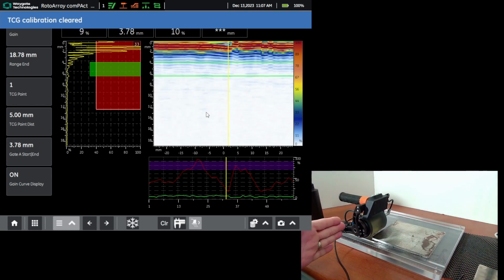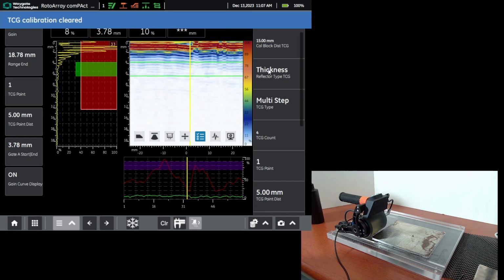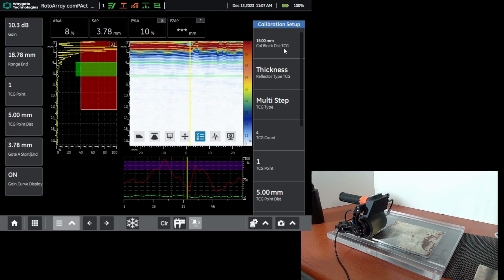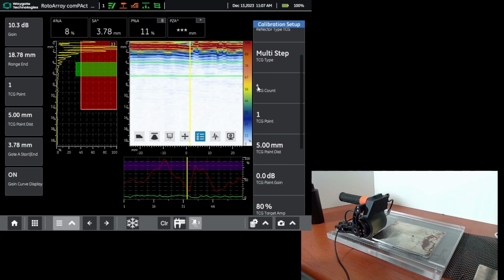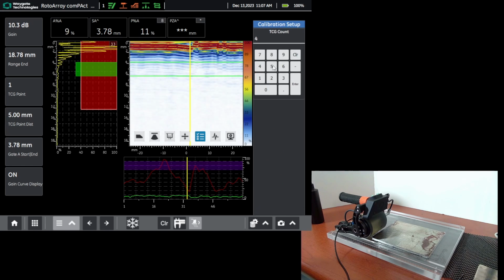Now, before I go through the actual calibration, I need to do a little bit of setup. So if I click on my eScan and on the procedure menu, we'll clear that message at the top for the moment. We're going to do a multi-step calibration. We're going to calibrate 4 points.